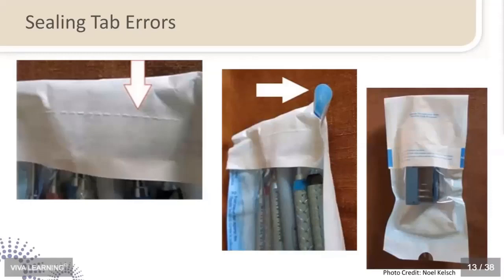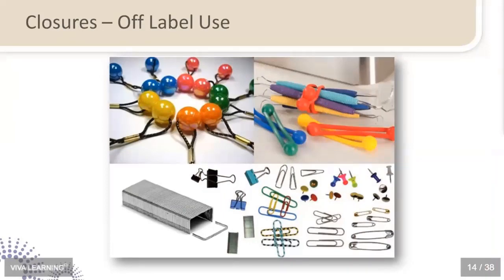And then again, the last one, somebody used too big of a pouch and they were trying to save room, and so they folded it down over, and it's folded 100% on the laminate. So you do not have a seal on that pouch. Basically, these are not approved for use with a medical device.